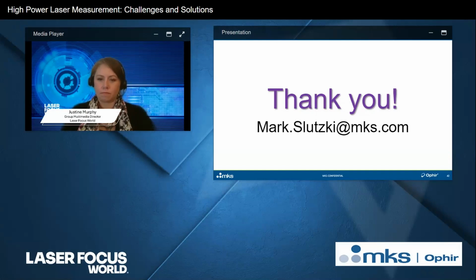And then to this, you might need to add other uncertainties if they exist. Usually the data sheet gives additional uncertainty with this or with that. I should just add two side points, since whoever's asking this is obviously very familiar with these QA issues. So one, this assumes that the reading is from around 5% of full scale and up. If you're measuring right near the floor of a given range of a sensor, you might start getting into linearity issues and your accuracy is going to be affected. And two, I should just point out that our specifications are based on a 2 sigma standard deviation. If anybody doesn't know what on earth I just said, then don't worry, but whoever asked that question obviously does. So I just have to mention that again for completeness.